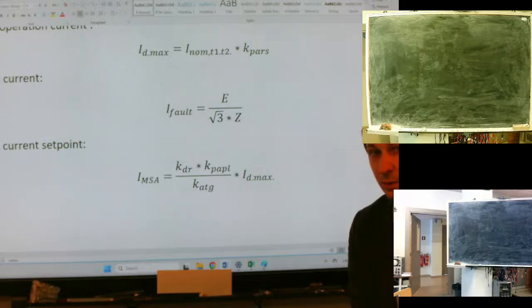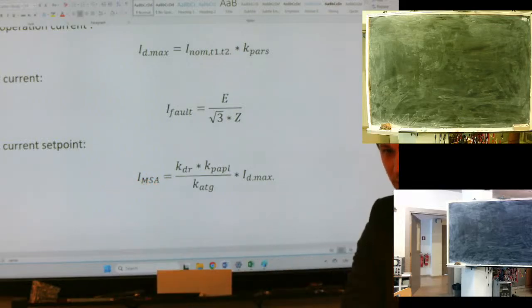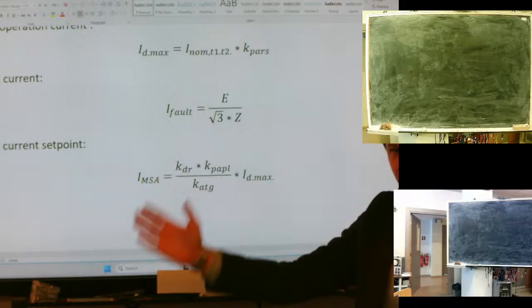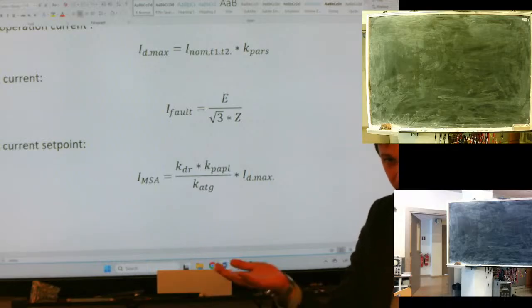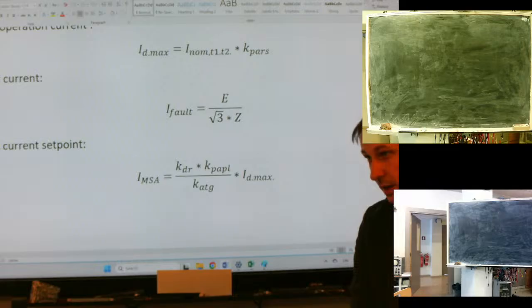There is no simple answer about the sensitivity, because as we understand, the greater sensitivity we have, the better. So, because it is very clear, if we have a fault value of 1000 and a set point of 100, we could be safe that if such a huge fault current appear, relay probably will detect it, because there is a huge difference, yes, between the set point and the fault value. But what is the minimum possible sensitivity that is good enough for us to be safe?